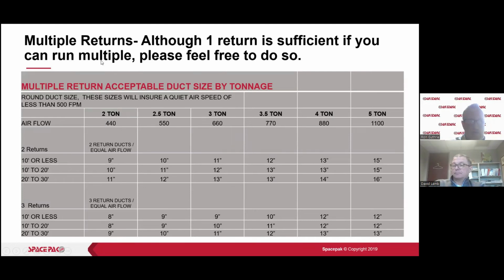All right, the way this works, this initially came from zoning. And the way it works is if you have two returns, then you're going to take a look at how long each return is individually. If you had one that was 10 feet and you had one that was 15 feet in a 2-ton, then you would use a 9-inch duct. Okay, but I'd probably up that to 10. And here you'd already have that 10 right there. So you might want to use both 10 with respect to that.